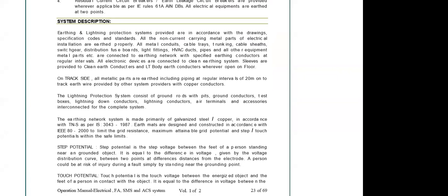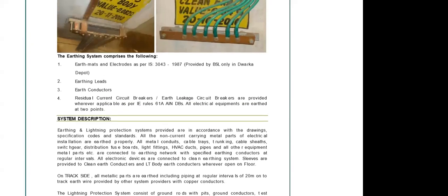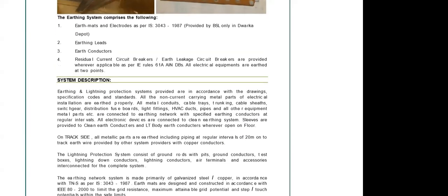So basically in the system, we are providing two types of earthing: the main body earth, like if we consider that LT panels are done with the main earth, and the voltage level is 450. In case of single phase and sophisticated equipment like BMS, UPS, DG sets, transformers, DC transformers, I mean traction transformers, there we do the clean earth, and it is separated from that.